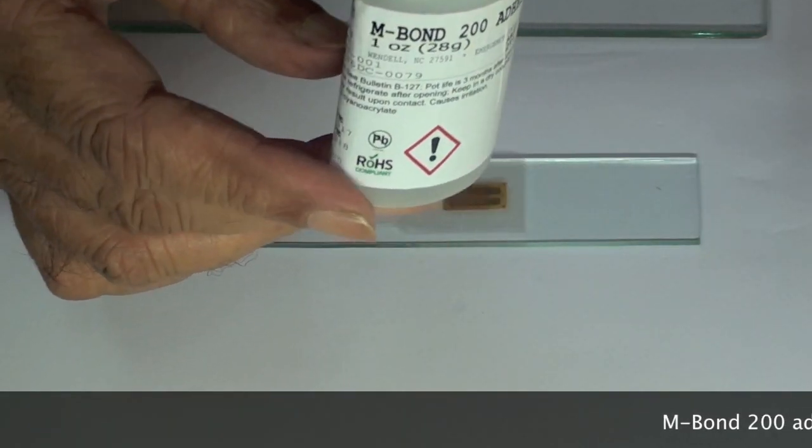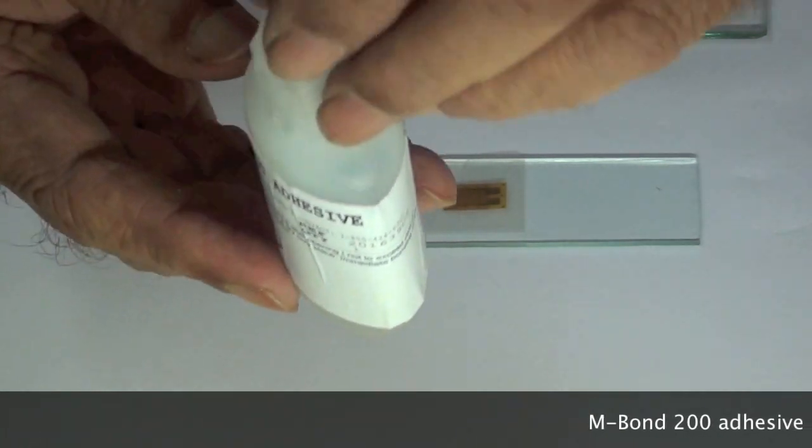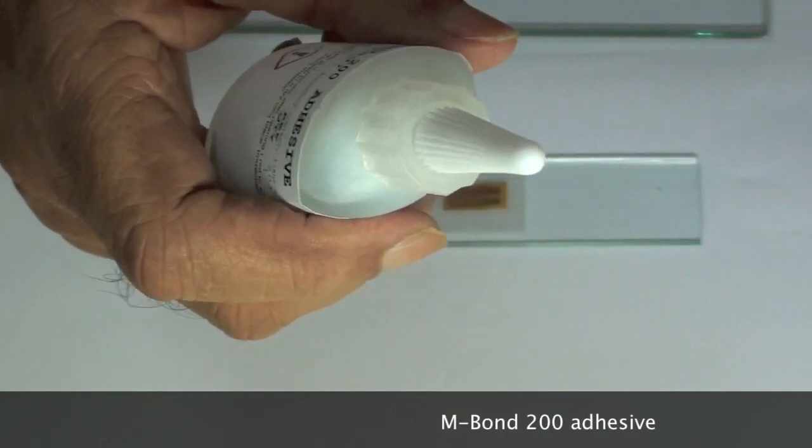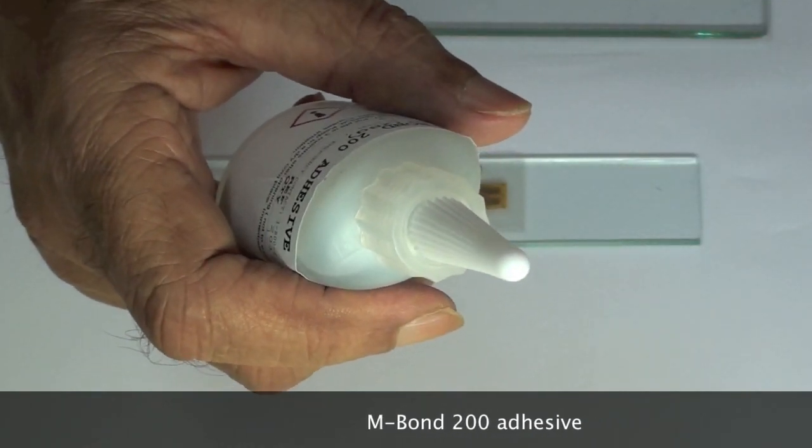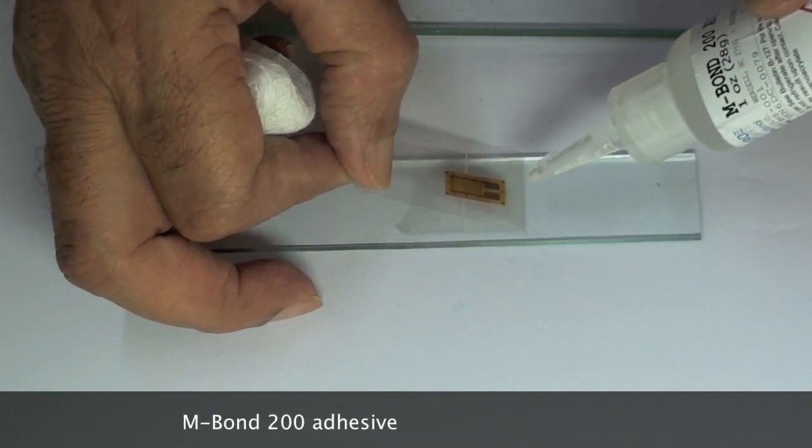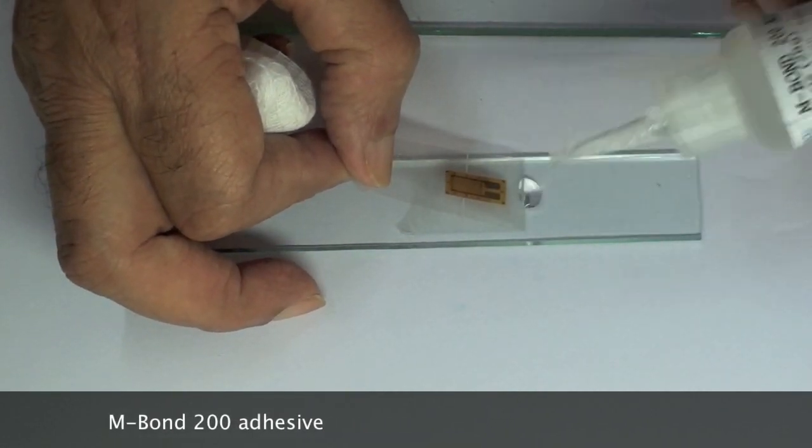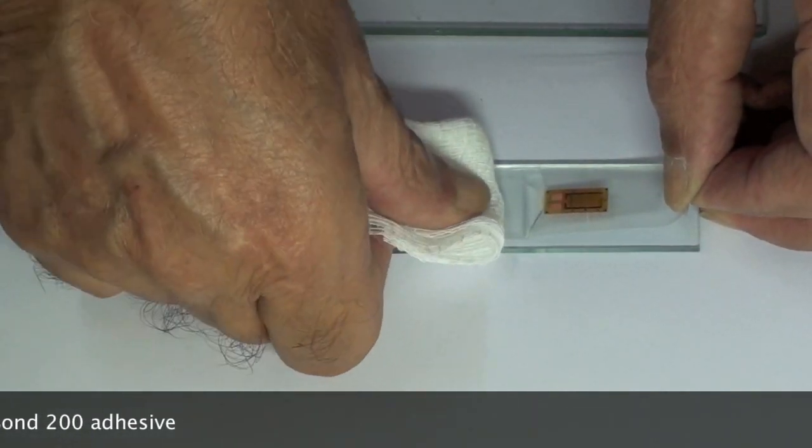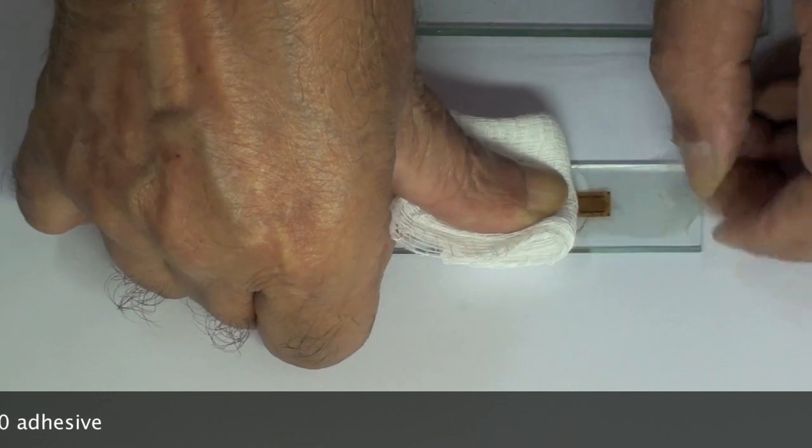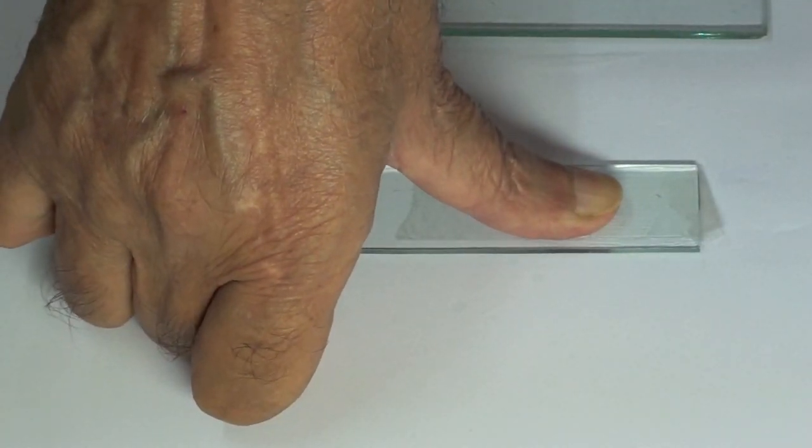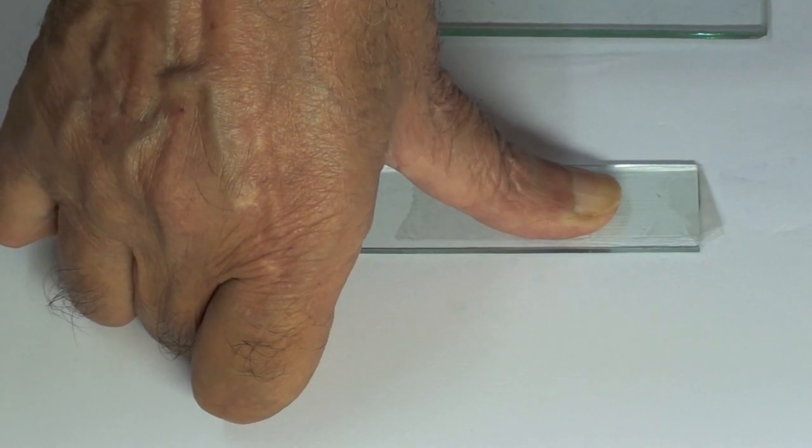When the tape holding the gauge is held at an obtuse angle to the surface of the part, a drop of M-Bond 200 adhesive is placed at the join of the tape and the part's surface. The tape is then held over the surface at a shallow angle and pressed down with a smooth sliding action using a folded gauze pad, pushing out all excess adhesive all the way to the end of the tape.